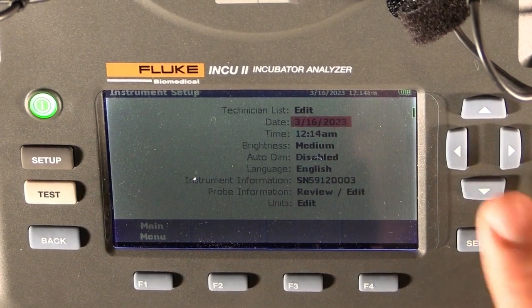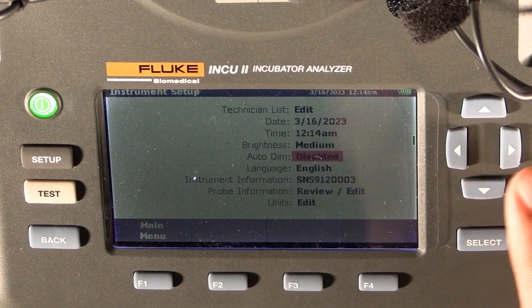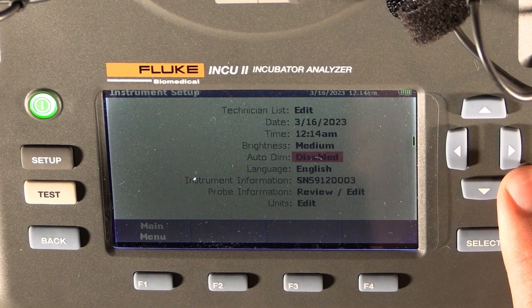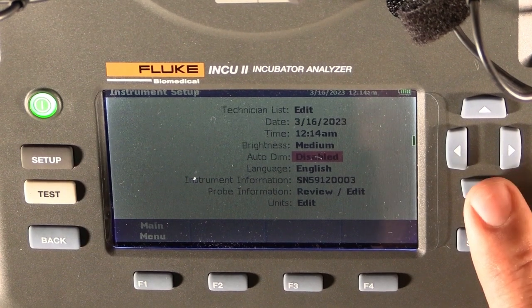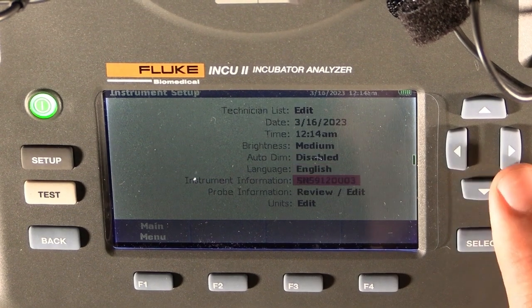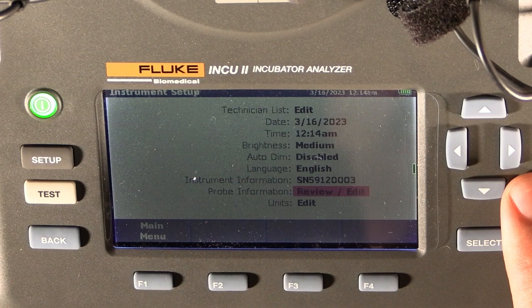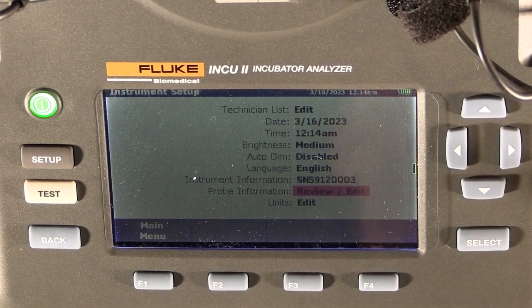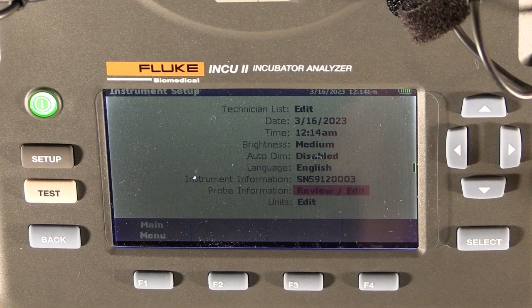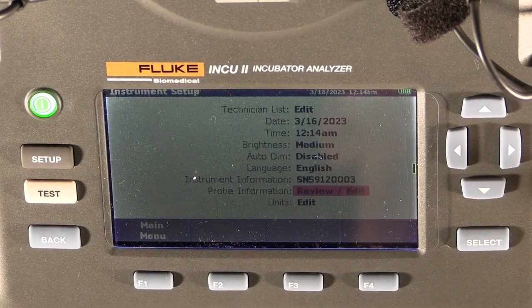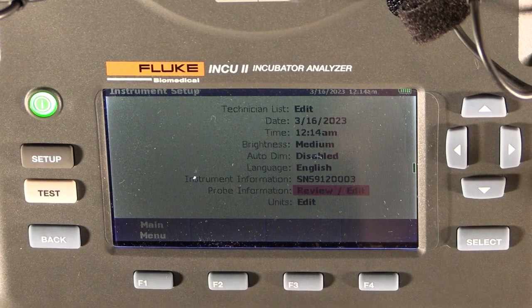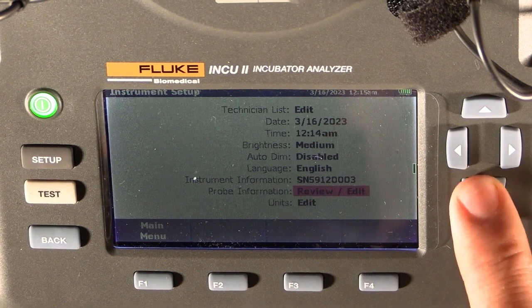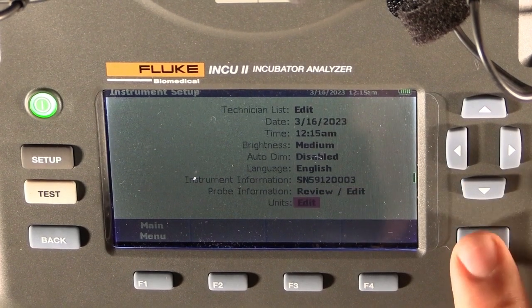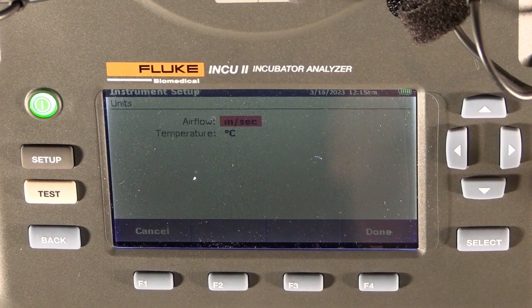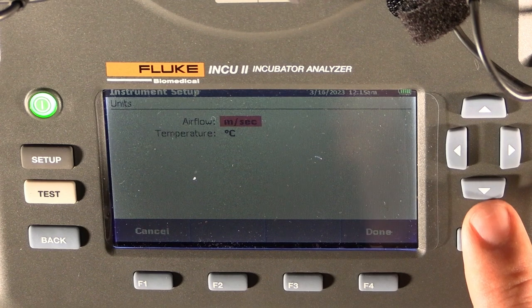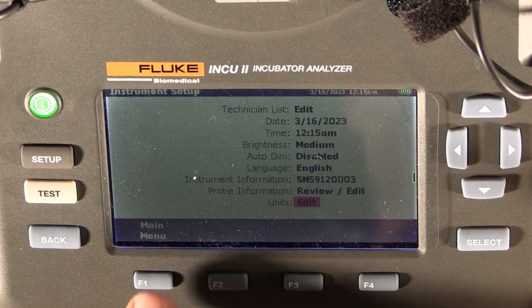Secondly, we can change the date of the unit. Thirdly, the time, the brightness, auto dim, meaning like in your cell phone, during the day and during the night, it automatically changes the screen brightness. The language, the instrument serial number, probe information. The only time you're going to use that is if something goes wrong with one of your temperature probes, for instance, and you have to replace it. Each probe has a calibration constant, and you will have to enter the new calibration constant. And then lastly, the units. If we press select, that is where we choose between meters per second or Celsius or Fahrenheit or all those units. Done.